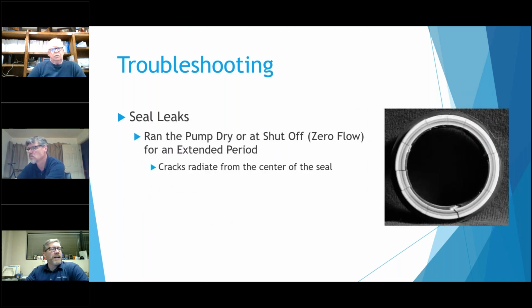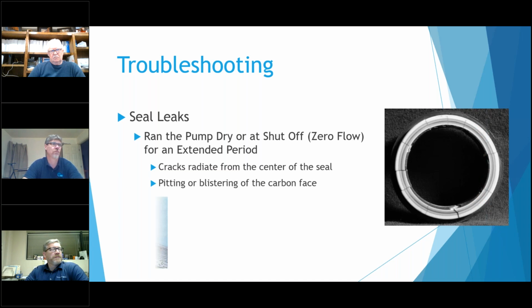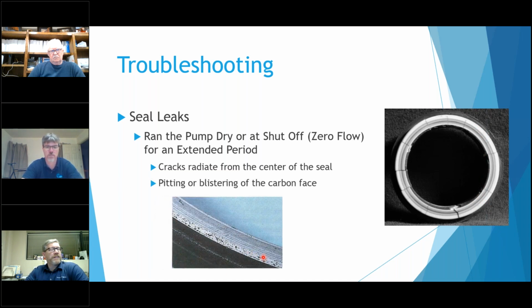This is what a seal looks like when it's been run dry. It will have cracks radiating out, or you'll see blistering on the face. So sometimes it tells the story of what happened to these seals, and you just don't always want to immediately throw them away.